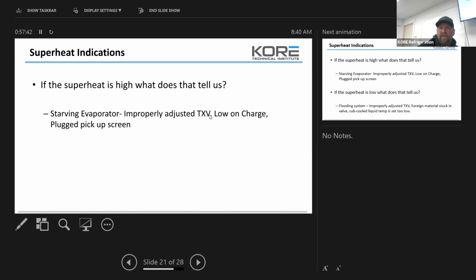If the superheat is high, what does it tell us? A starving evaporator. That could be a plugged screen on a TXV, or an issue with the TXV, a power head issue, or non-condensables causing it to ice up. So there's a problem with your metering device. If you're dealing with a cap tube, it could be a restriction in your cap tube.